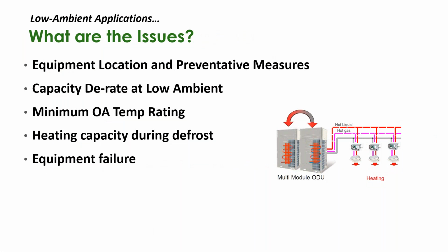So low ambient applications, what are the issues that we're looking at here? First and foremost, when you're applying any HVAC system in cold climate, you've got to consider the equipment location, keeping it safe, keeping people safe around it, and preventative measures to increase the longevity of its life cycle. We have to consider the capacity derate on heat pump systems, low ambient conditions, as well as manufacturers' minimum outside temperature ratings for that equipment. What happens to your heating capacity during defrost is also something we need to look at, as well as the dreaded catastrophic equipment failure and how to plan for that.